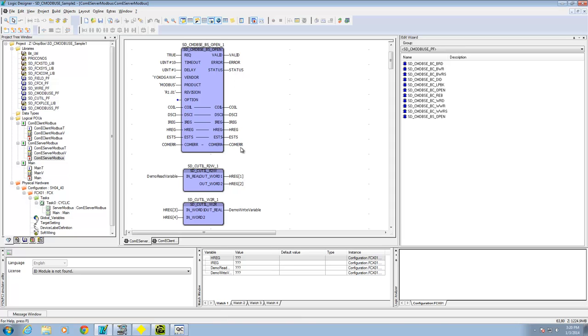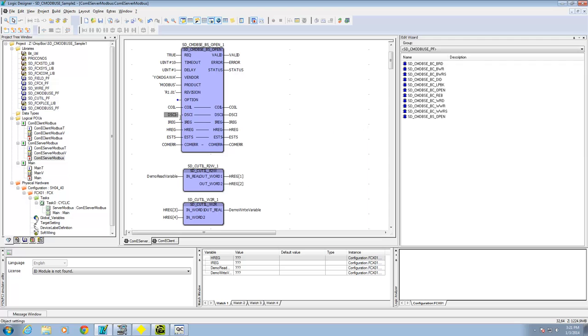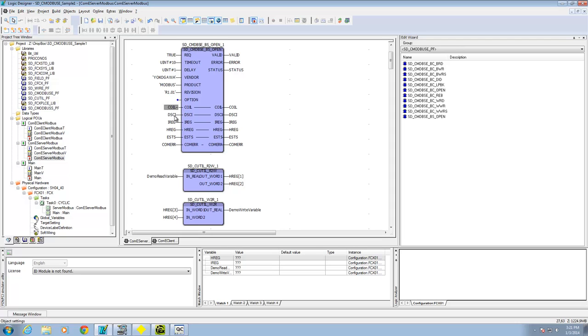You'll need to fill in some of the parameters for that block. For these inputs, you'll need to attach some arrays — here's a coil array, an integer array, and a holding register array. If you double-click on them, you'll see they are type word. That one is also type word, and these others are bit or binary type. The data types are already defined — you essentially just need to provide names, and these arrays are what gets served up.